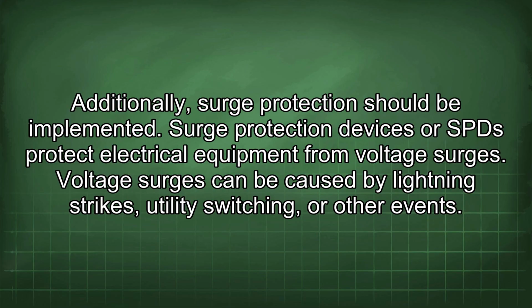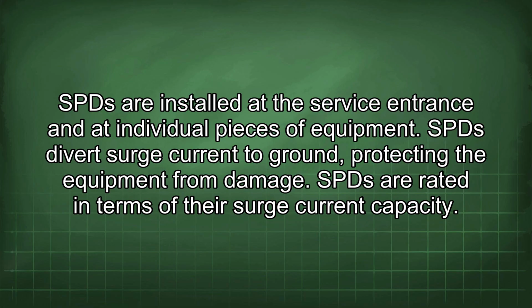Additionally, surge protection should be implemented. Surge protection devices, or SPD, protect electrical equipment from voltage surges. Voltage surges can be caused by lightning strikes, utility switching, or other events. SPD are installed at the service entrance and at individual pieces of equipment. SPD divert surge current to ground, protecting the equipment from damage.